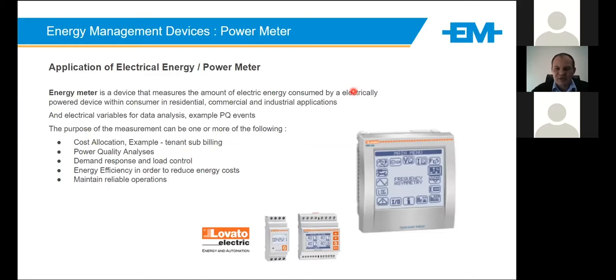What is the purpose? Typically purposes would be cost allocation, tenant sub-billing, power quality analysis. You may have some sort of issues that you need to dig a little bit deeper into the electrical content of that network. Demand response, load control. So based on data, on peaks, to set a sequence of events to control those loads. Seeing energy efficiency to see if there's a place to reduce. And then maintenance, general failures that you would pick up based on electrical data. Say, I know that meter should be seeing load and is not seeing load. Maybe the motor's not started or something has occurred.